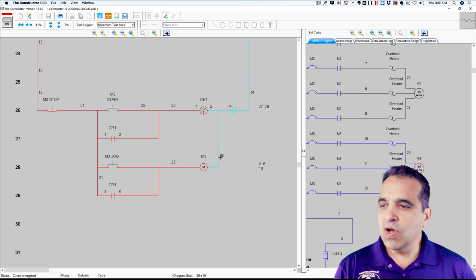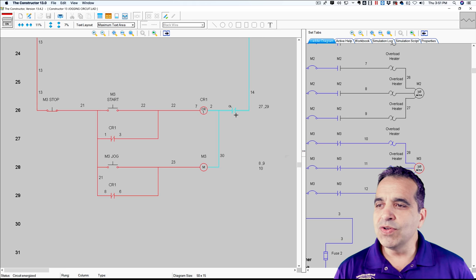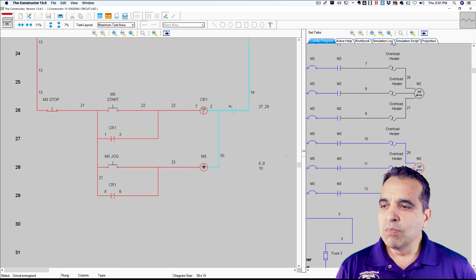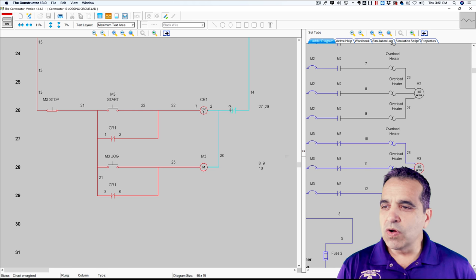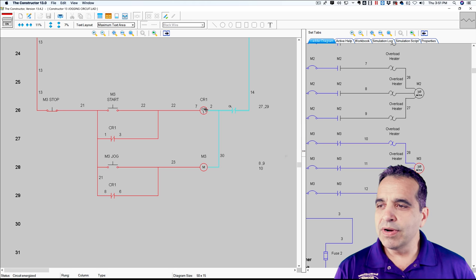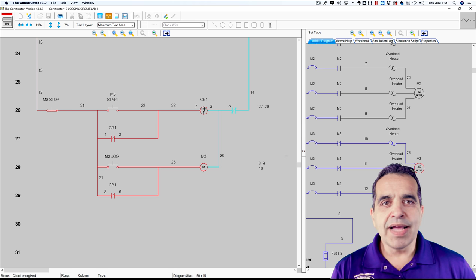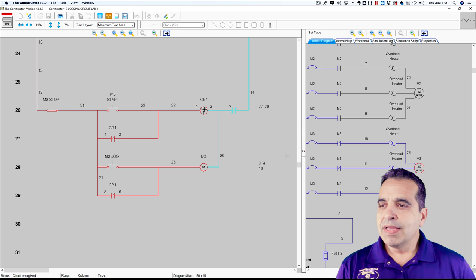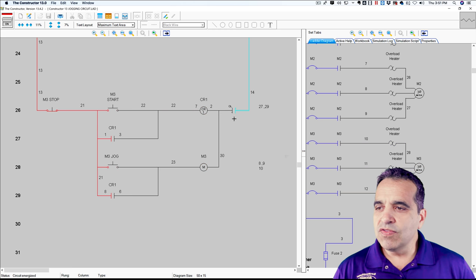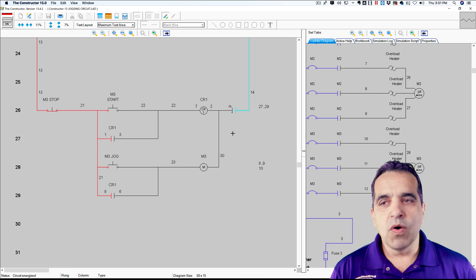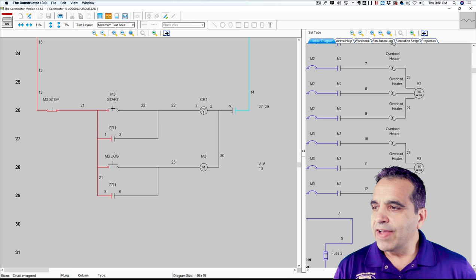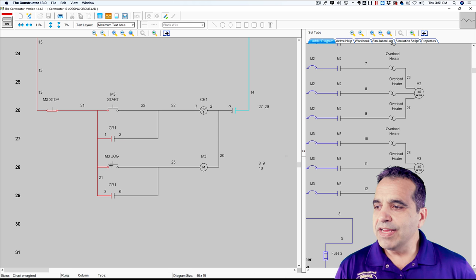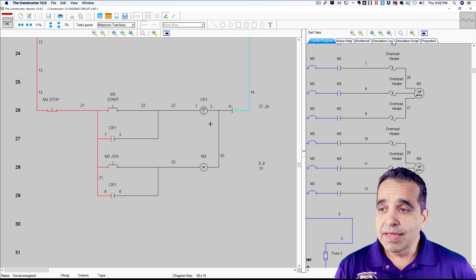Now, if you'll notice, I have the neutral to my motor coil on this side of the overload. And the overload is controlling both my motor and my ice cube. That's really important because if I lose my overload, my overload tripped, if I come over here and try to start, it won't start. But if I come down here and try to jog, it won't jog.